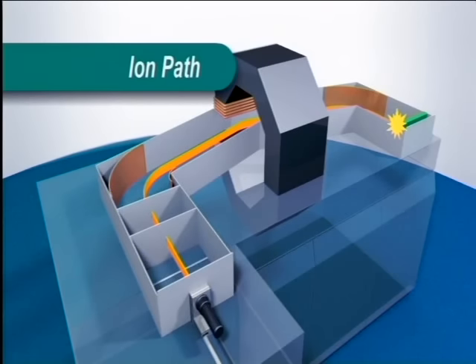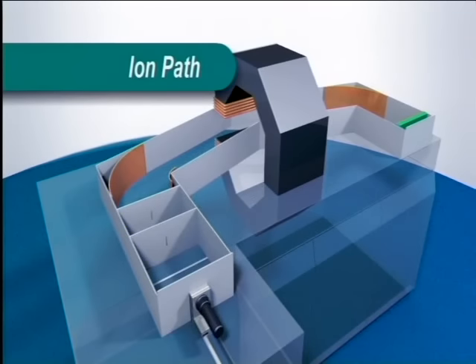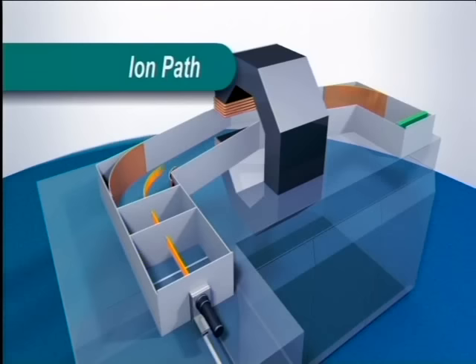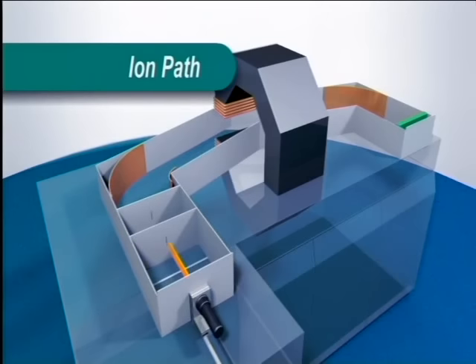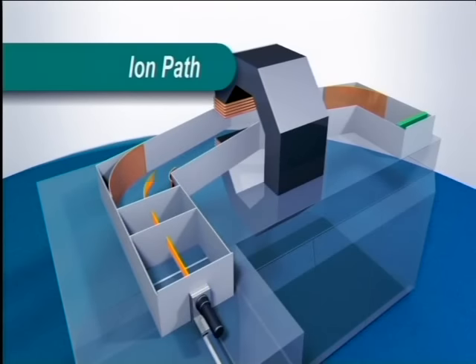The amount of deflection by the magnetic field depends on the mass of the ion — strictly its mass-to-charge ratio — but the vast majority of ions have only a single charge. The deflection also depends on the strength of the field. Heavier ions will not be deflected sufficiently in the magnetic field to reach the detector; light ions will be deflected too much. During a run, the magnetic field is gradually increased so that ions of successively greater mass enter the detector.